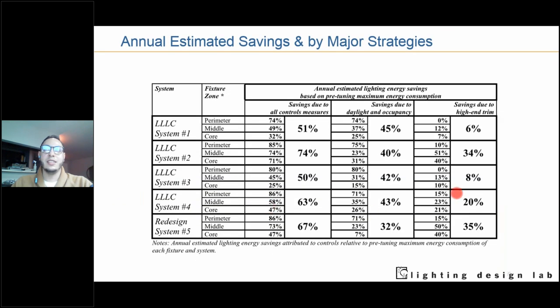When it came down to savings, the network lighting control system had the most savings for high-end trim, but when it came to daylight and occupancy, it had the lowest tier of savings because there are more sensors in each of the luminaire level fixtures—it's more granular and can drive further savings. When we looked at all the control measures, the redesign system did not really save that much more energy than the other luminaire level lighting control system, so they were rather comparable in savings. The NLC system just had a lot higher costs.